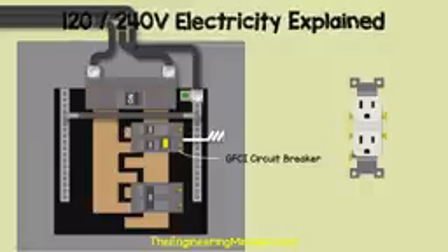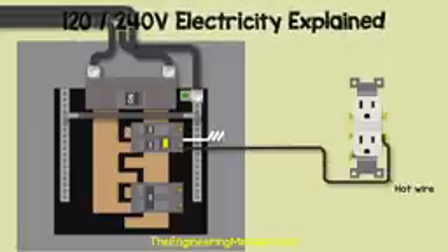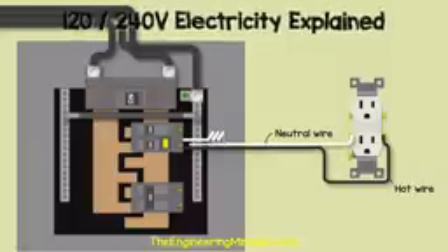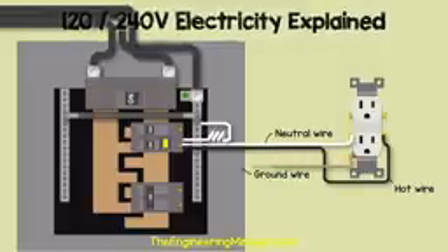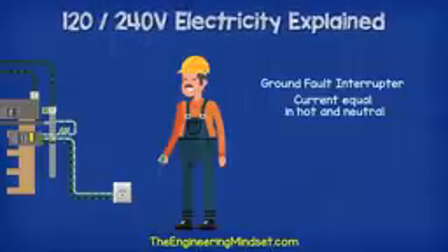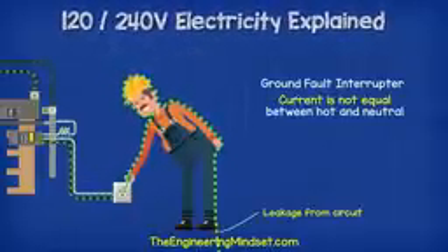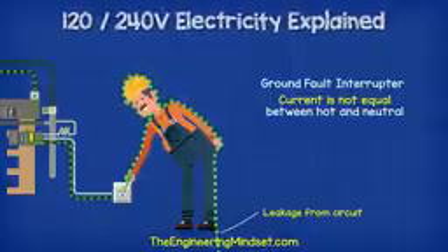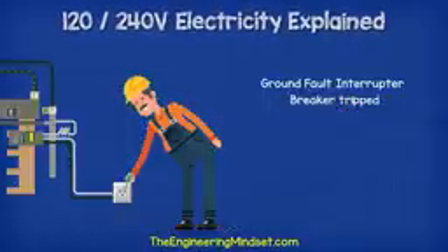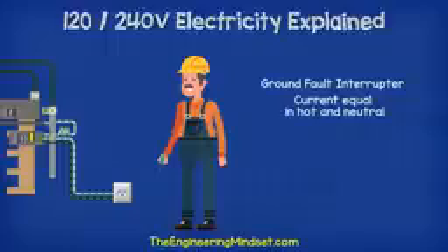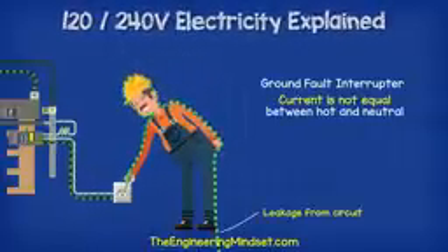If we took a standard outlet, we would take our hot wire from the breaker and connect this to the outlet terminal. Then we take the neutral wire and run this back directly to the circuit breaker to a specific neutral terminal. We then connect the pigtail wire into the neutral bus bar. This will provide the return path. And of course, we run the ground wire from the outlet back to the neutral ground bar. If we look at this example, the current is flowing normally until the guy sticks a screwdriver into the socket. The electricity then flows through him instead of the neutral wire. The GFCI is measuring the current in the two wires and notices that these are not equal. It then automatically trips the breaker to cut the power and save the man's life.